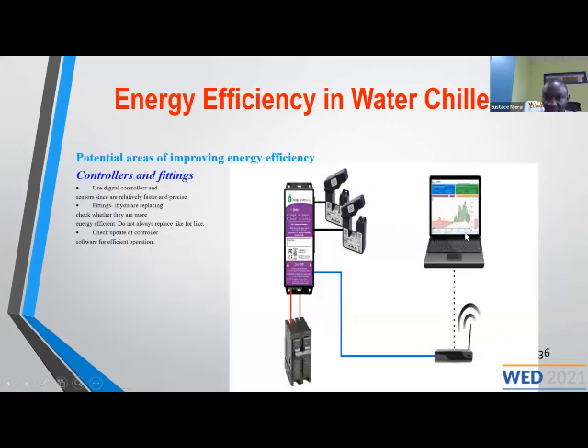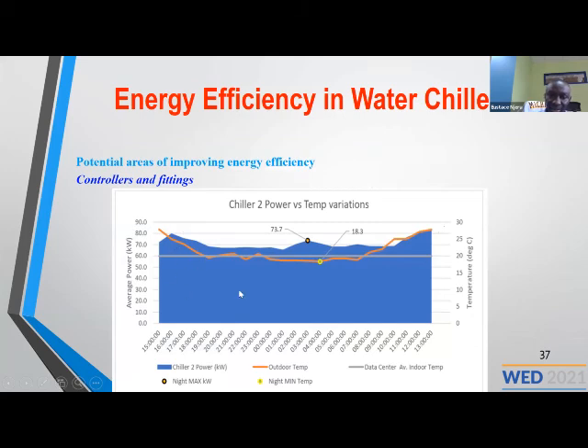Some of them you can even do remotely. You can use an e-gauge system in a remote way. In the morning, we talked about real-time monitoring. You can use that to control. In one of the systems, you can see that as the outdoor temperature was decreasing, the power was not changing a lot, even sometimes increasing, even when it's very high. There's a real case of a bad control system. You can see here, if the controls were good, you could have the power dropping and the temperatures dropping.